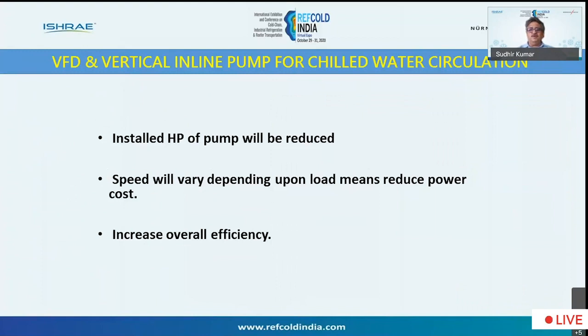Say for example, now at this point of time, you are only requiring 100 meter cube per hour and your pump is 150 meter cube per hour. You can use a variable frequency drive, reduce the speed, and only pass on 100 meter cube to your process. So indirectly, it again reduces your load in the PHE or IBT system, and your compressor unloads and saves power. So this is one of the very good developments in the chill water lines, where you will have vertical inline pumps and variable frequency drive.